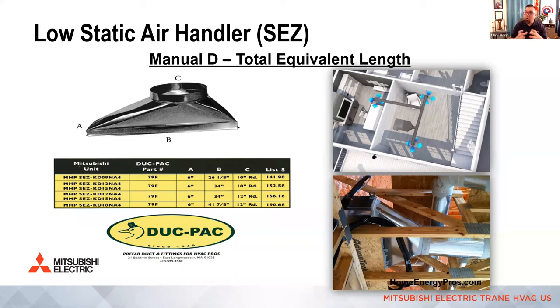If you go to something normal like round trunk, just make sure you take the takeoffs at an angle off the side to keep the lowest values. Andy mentioned with no dampers, how do you balance? Yeah, it's going to be really important with low static air handlers that we keep the zones very small. It's one or two rooms, and you shouldn't need balancing if you size the system correctly, okay? When you're doing an entire floor, balancing is very important, and you shouldn't be using a low static air handler.